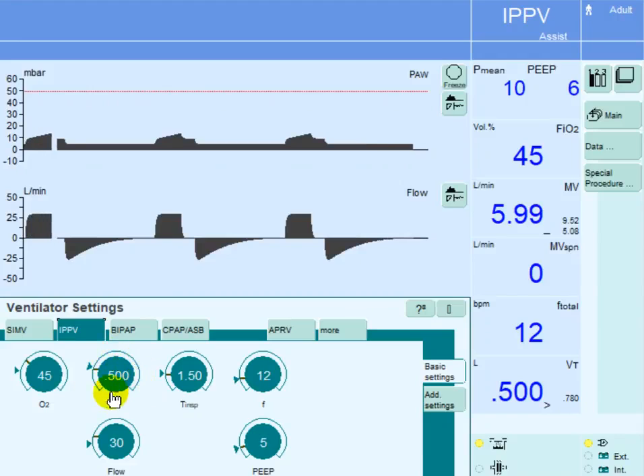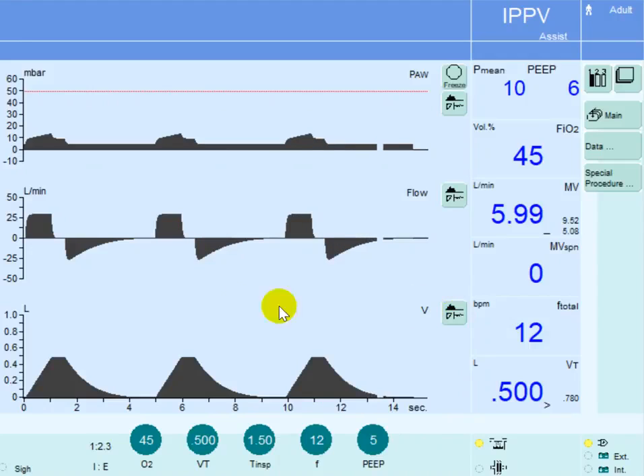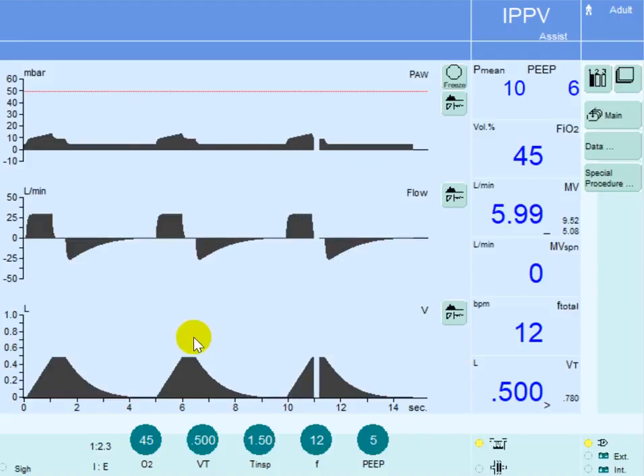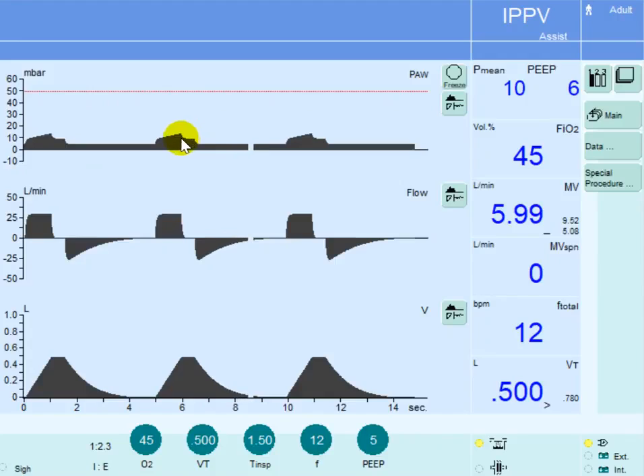Since we are able to deliver 0.5 liters at a flow rate of 30 liters per minute in one second, that means we are left with 0.5 second in inspiration where the volume is already into the lung and the flow reaches zero. There is no need for more flow to deliver any further volume. In order to keep that volume inside the lung, we need to overcome the lung elastance — that's why we need a pressure here, which is a plateau pressure. There is no more need for pressure to overcome the airway resistance, which is why the peak airway pressure goes down to the plateau pressure.